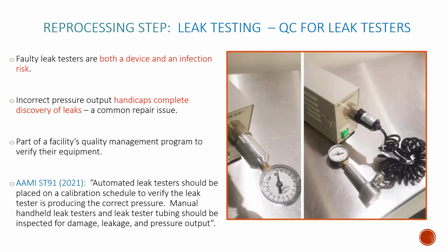For the step of leak testing, once again, following IFUs is reinforced. And here it is both the endoscope manufacturer's IFU as well as the leak tester manufacturer's IFU. AORN and AAMI highlight the need to perform and document pressure outputs from leak testers to help ensure any and all leaks are identified. The rationale here is that if a leak tester is not delivering correct pressure outputs, leaks can be missed, and any leak matters, however small or large. This pressure output quality control testing would occur whether it be an automated or manual leak tester. For AAMI, this would be done each day that endoscopes are used. Any scope failing leak testing or discovered to be damaged should be individually labeled or tagged and managed per facility repair policies.